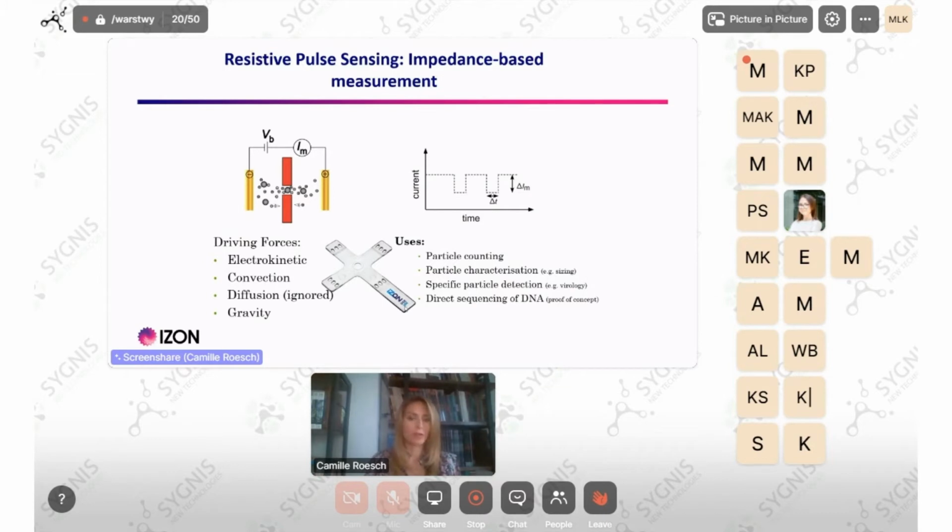As I told you, those nanopores are consumables. That means that they're not going to last forever, but you don't have to change them every day either. Obviously, it depends on the intensity of your work, the intensity of your measurement. We like to say that each nanopore would last for around 10 measurements. So if you're measuring 10 different samples on a single day, then yes, you're losing 1 nanopore a day. Some of them, like the bigger nanopores, would be a little bit more robust than the smaller nanopores.